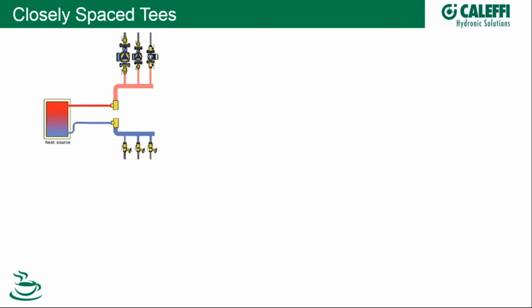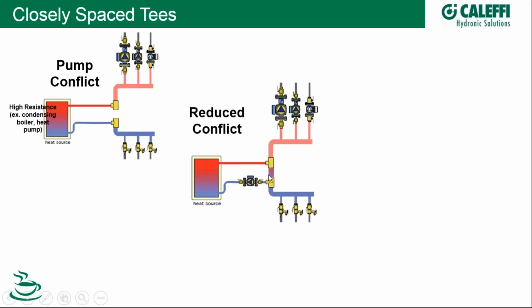A third example that I can think of in the heating and cooling world is, say, a typical centrifugal chiller application. As I mentioned, chilled water has just as much need for decoupling of pumps as heating systems. But in those big chilled water systems, until now, it's often been most economical to create a bypass here, if you will, simply by using piping and having the piping sized in diameter wide enough to accomplish the task of minimizing pump conflict. Okay, and those would be three examples I can think of. Now, you could use a hydraulic separator in that case, and you get the added functionality, especially in a 3-in-1 or 4-in-1 device, of all the other benefits like air separation and dirt separation. And you might even be better off that way. But that would be an example where just a pipe, a decoupler pipe, sometimes seen on drawings, can be used instead.